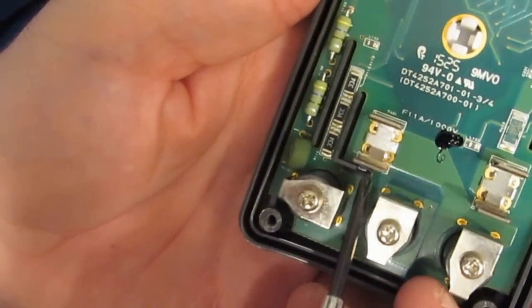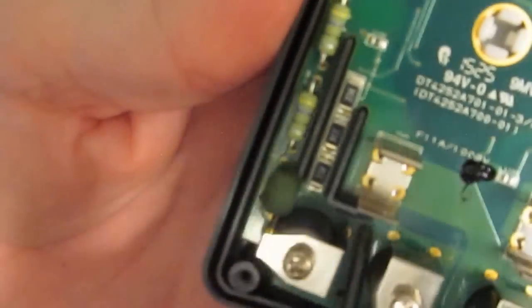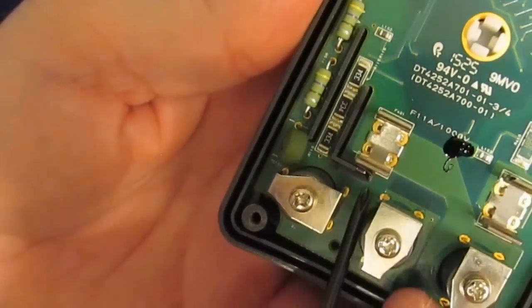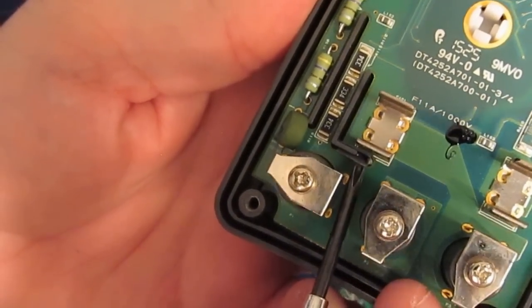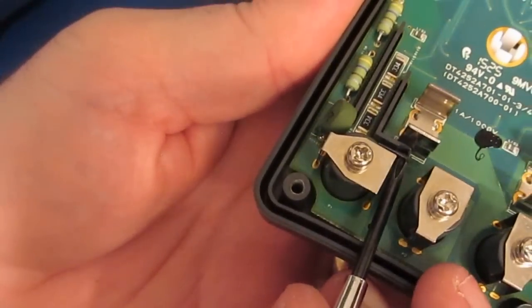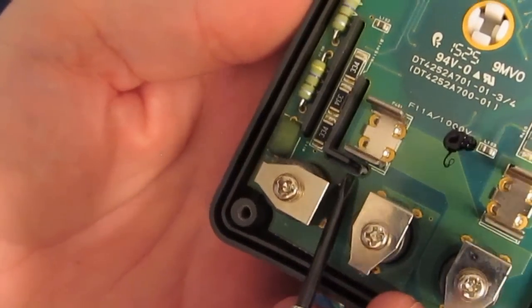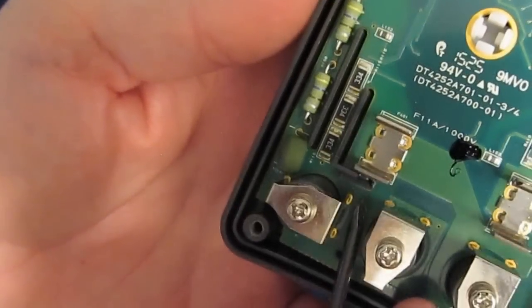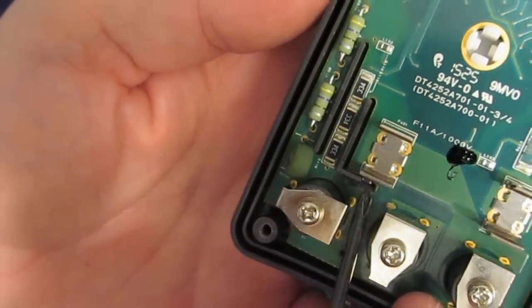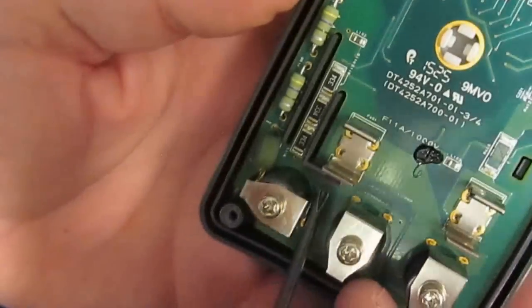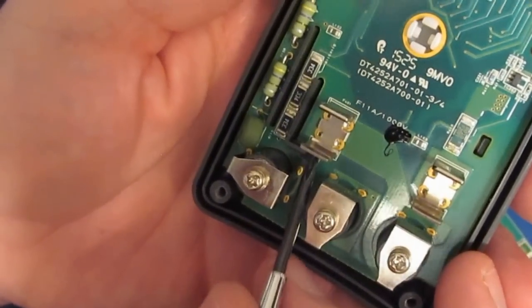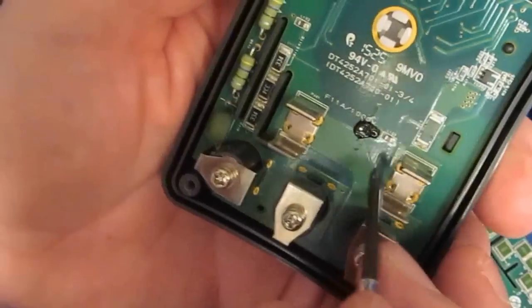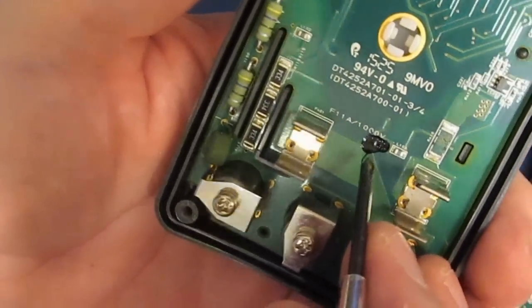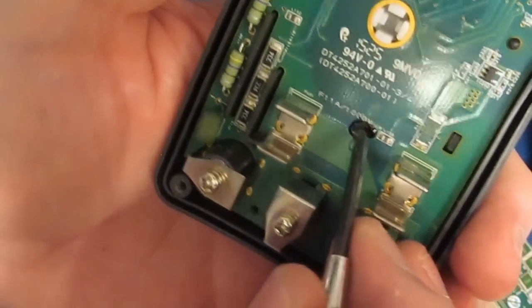I think I tested this meter all the way up to 14 or 15 kV. What ended up happening is the transient worked its way around this little plastic insert, and you can see I've bent another little plastic insert here to increase the length and force the transient to have a further distance to travel. That allowed me to continue testing this meter even higher than where it originally broke down. You can see I've added a bit of corona dope right in this area.